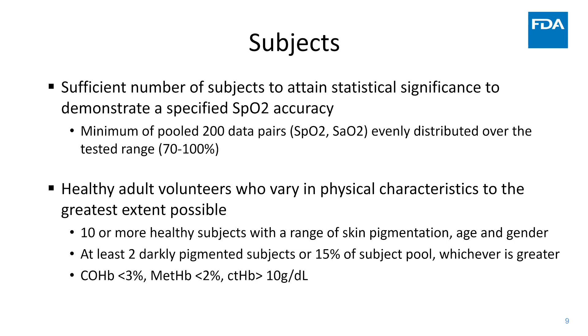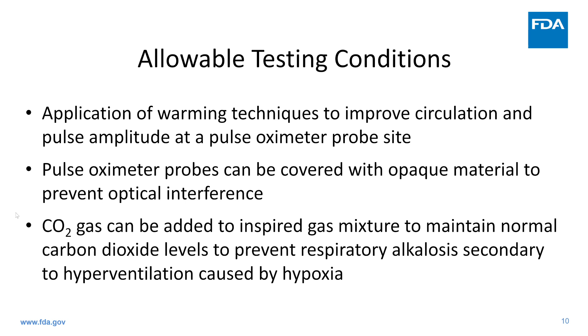Per ISO standards, allowable test conditions for pre-market desaturation studies include application of warming techniques to improve circulation and pulse amplitude at the pulse oximeter probe site, covering of the pulse oximeter probes with opaque material to prevent optical interference, and the addition of carbon dioxide gas to the inspired gas to maintain normocarbia and to prevent alkalosis secondary to hyperventilation caused by hypoxia.